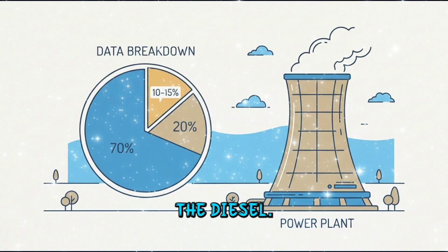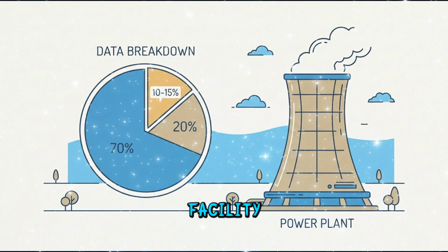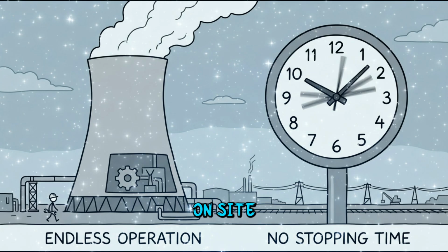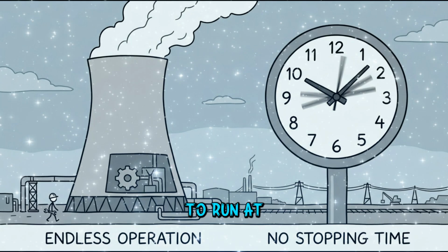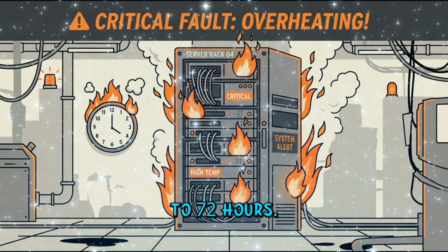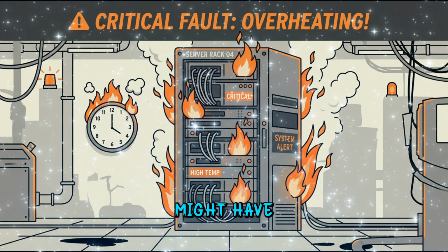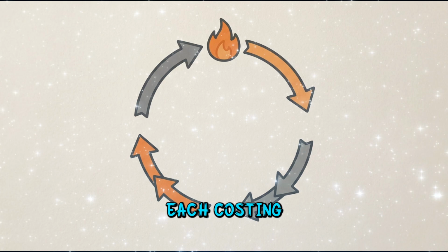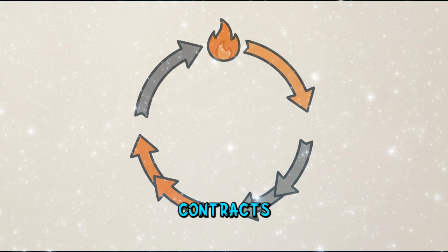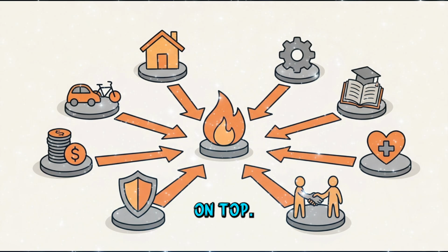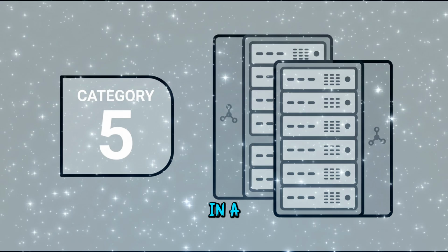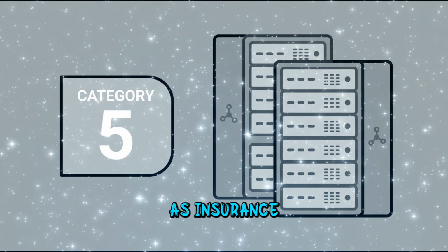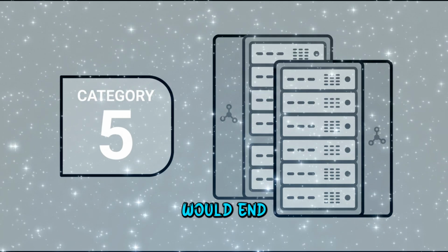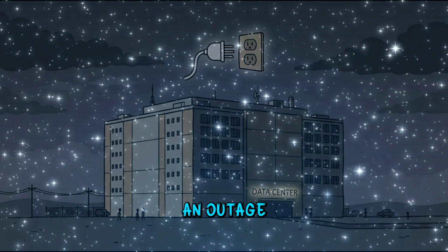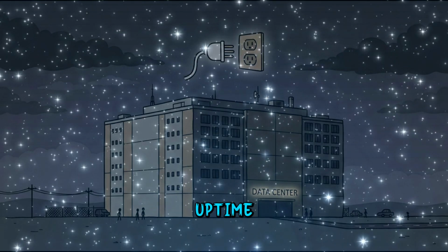Category 5. The diesel. Every hyperscale facility keeps a fleet of backup generators on site, with enough fuel storage to run at full load for 48 to 72 hours. A large campus might have 20 to 40 generators, each costing $1.2 million plus fuel contracts and environmental permitting on top. It's an entire fossil fuel power plant sitting dormant in a parking lot, existing purely as insurance against the one thing that would end the business instantly: an outage during a contractual uptime window.